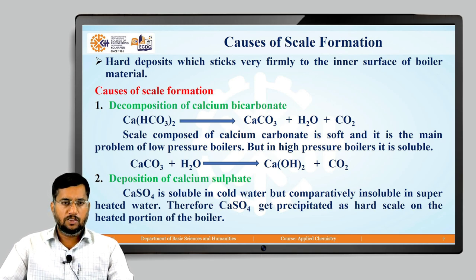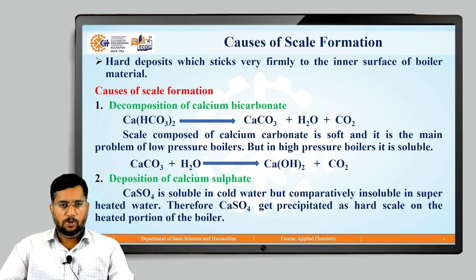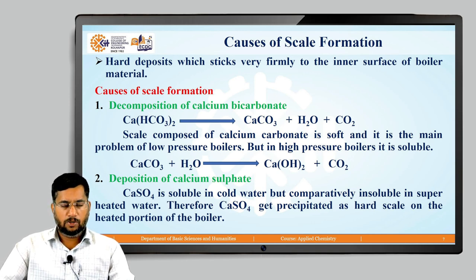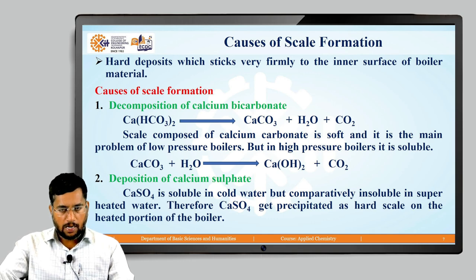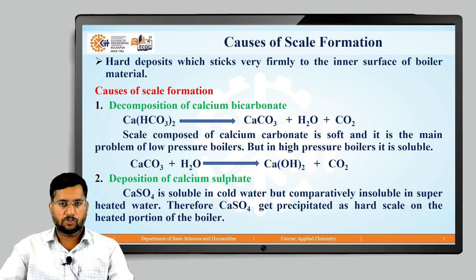The second cause is deposition of calcium sulfate. Calcium sulfate is soluble in cold water but comparatively insoluble in superheated water. Therefore, if boiler feed water contains even a small amount of calcium sulfate, it precipitates as a hard scale on the heated portions of the boiler, forming a hard adherent bond with the inner wall.